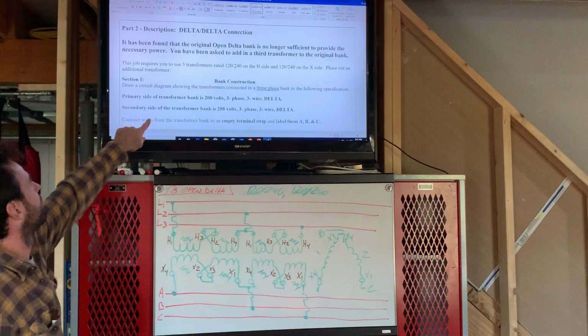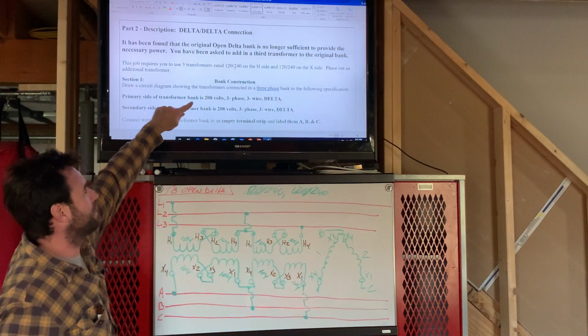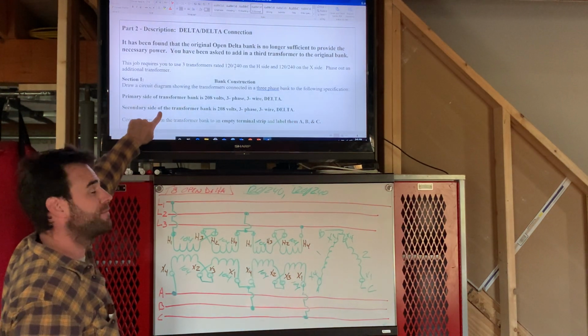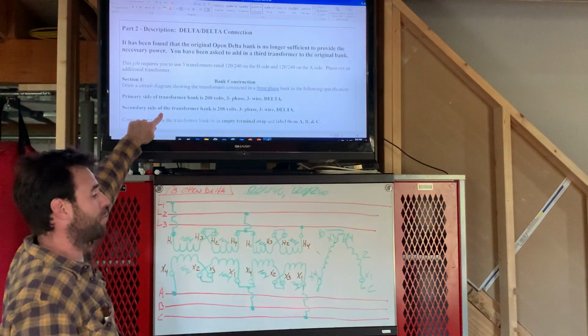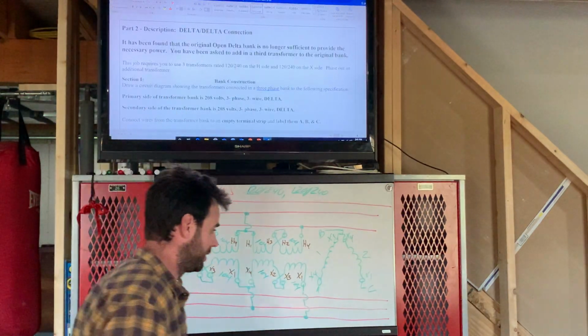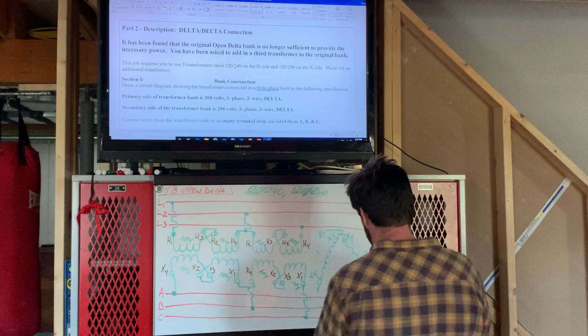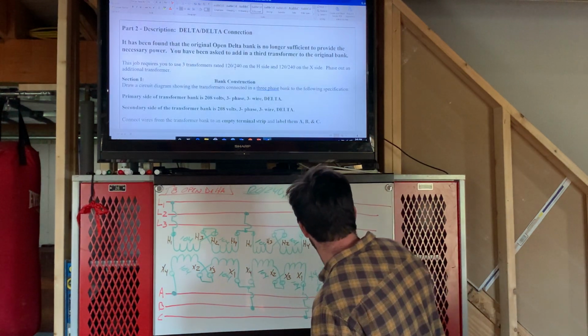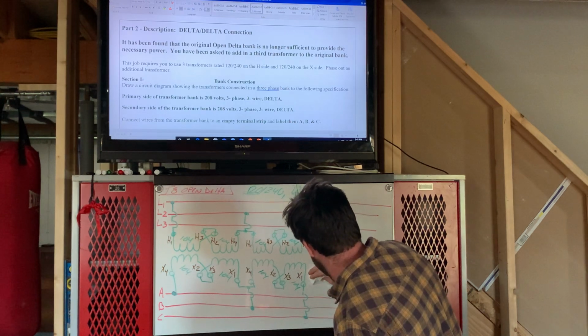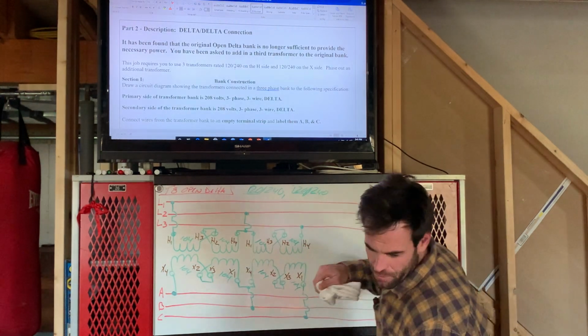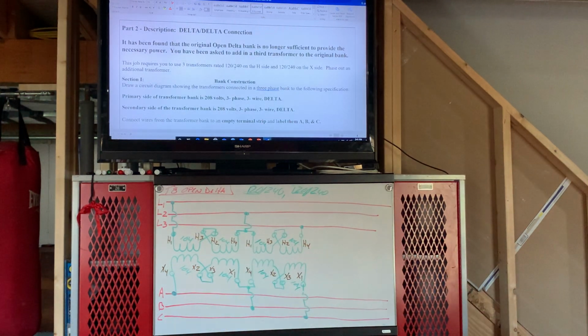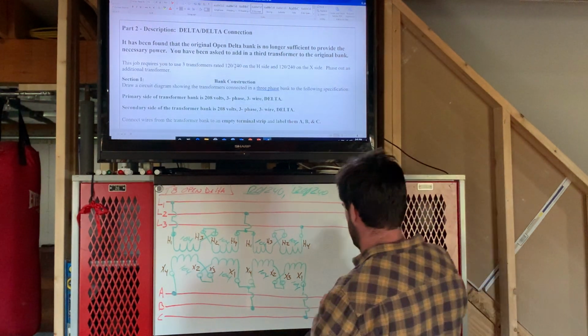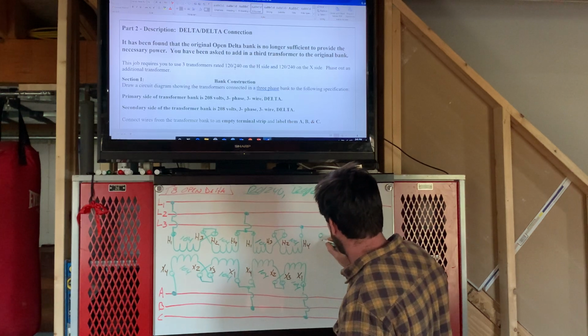So, primary side of the transformer, still 208 3-phase 3-wire. We want the same voltage out of the secondary, 3-phase 3-wire delta out of the secondary. Rag. So, erase this. So now you're going to grab your 3rd transformer. Here's my 3rd one.